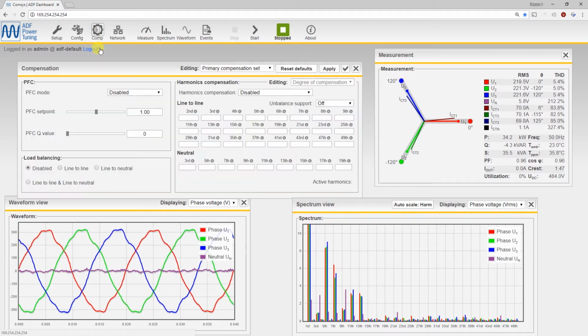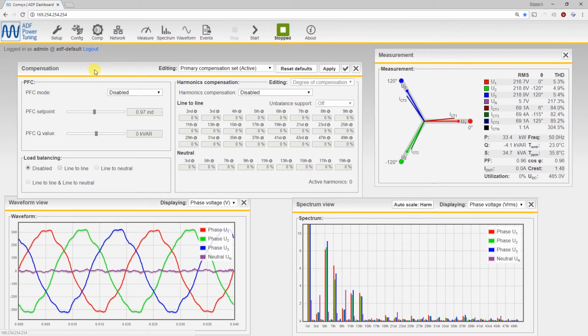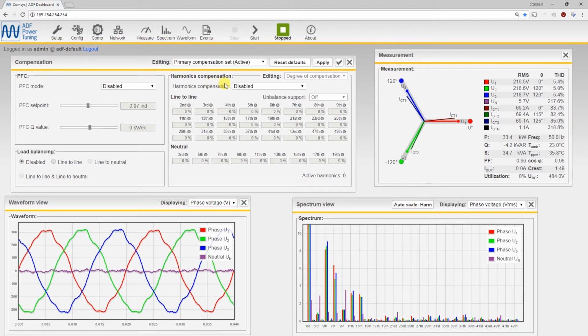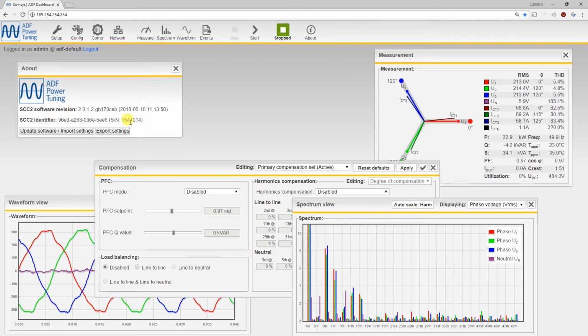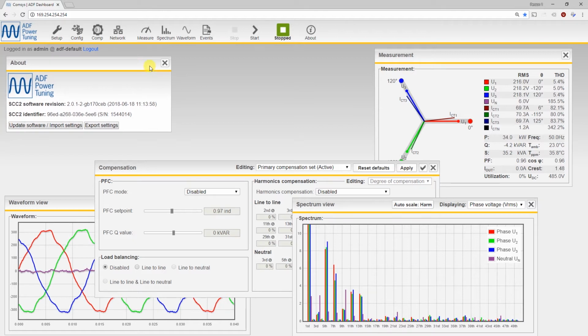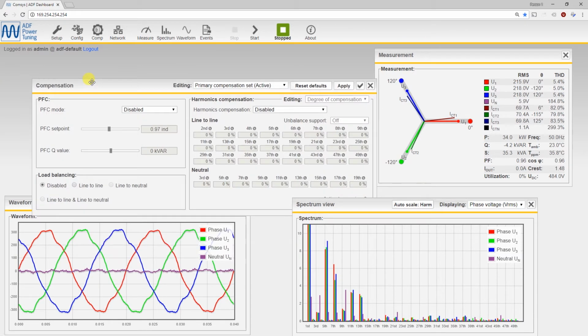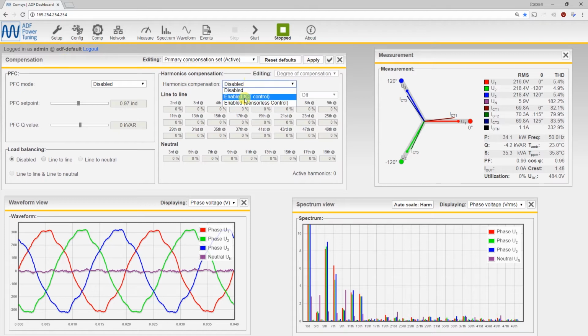The last window that we need is the compensation window. Here in the compensation window, as standard, everything is deactivated. So first we have to activate the harmonics compensation. We can do that now in CT control or sensorless control. If this one is grayed out, you still need a license key. Make sure you send in the about window the SCC2 identifier to Comsys, and with this identifier we can give you the license key. Now we have the possibility here to activate the sensorless control.